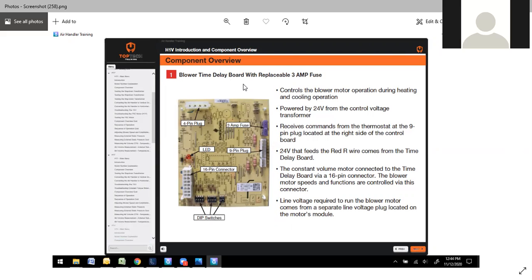This is your blower time delay. Once again, it has a 3 amp fuse built in. Controls the blower operation during heating and cooling operation. It's powered by the 24-volt transformer. Receives commands from the thermostat at the 9-pin right here, connected at the right-hand side. The 24-volt that feeds the red wire comes from the time delay board. The constant volume ECM motor connected to the time delay board is the 16-pin right here. The blower speeds and functions are controlled by this connector as well. Line voltage required to run the blower comes from the separate line voltage plug located on the motor module.